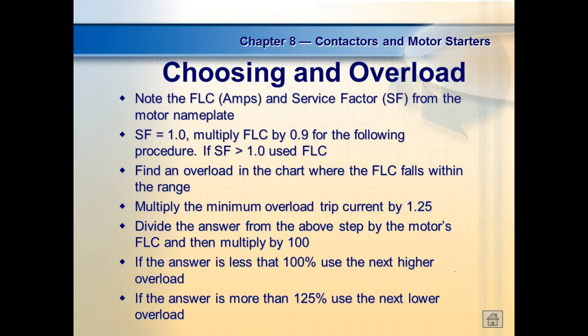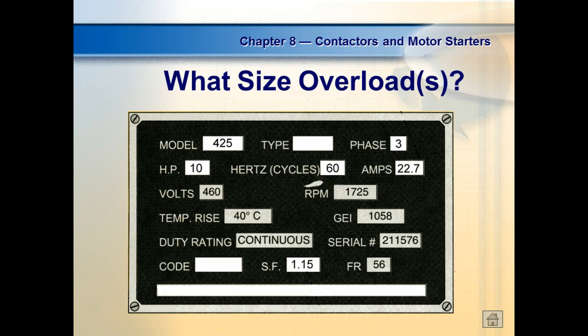And I want the model number. Are we ready? So this is a, how many phases? Three, so you're going to have three overloads. It's a 10 horsepower motor, and here's my full load current: 22.7 amps. And it's got a service factor of 1.15. That means we don't have to multiply by 0.9. We just use the full load current. We don't multiply 22.7 by the 1.15, that's already taken care of. All we have to worry about is if it's less than that. We don't do anything yet. Legally we could do it that way, but the overloads already take into consideration that the motor has a service factor greater than one.